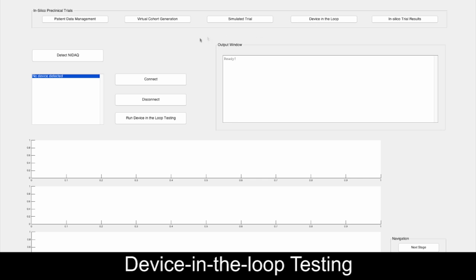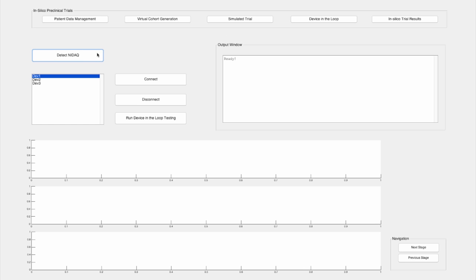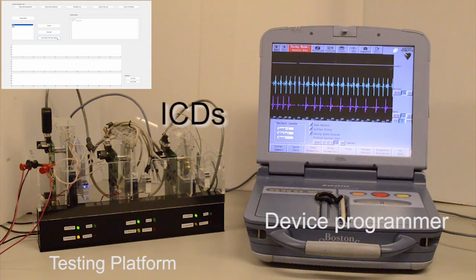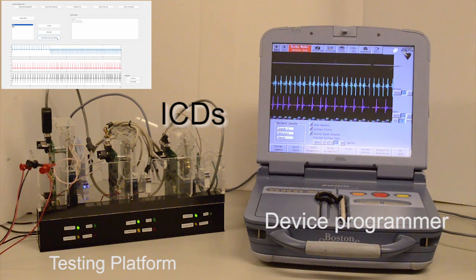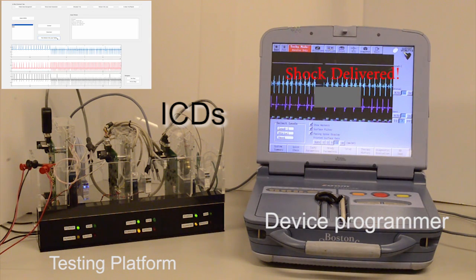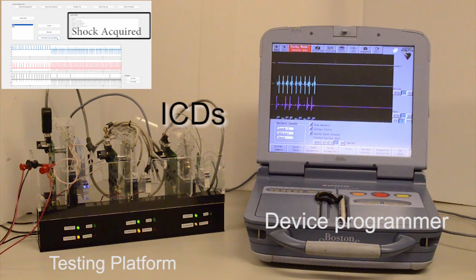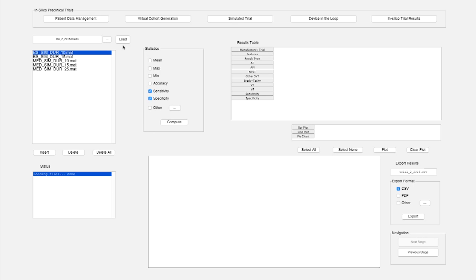In addition to device simulation, in silico trials support testing with the device in the loop. At this stage, the user can feed a real device with the signals from the virtual cohort. The synthetic signals are then fed to the real device through a data acquisition system, which can report whether a shock event occurs. You can observe the signals fed to the device through the toolchain on the device programmer. Now a shock therapy has been delivered and successfully acquired.